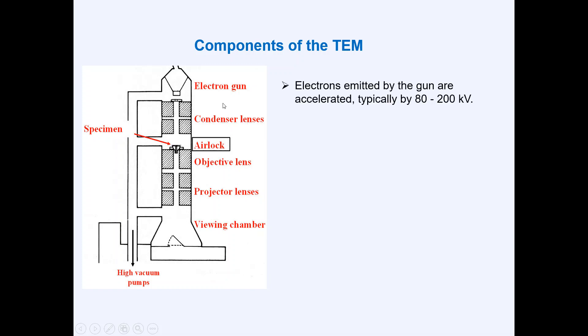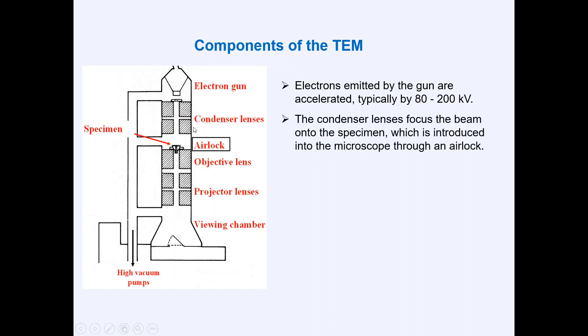Looking at the figure showing different parts of the transmission electron microscope: the topmost section consists of the electron gun, which emits electrons. Emission is achieved by applying a high voltage to the electron gun, which is normally made of tungsten or lanthanum hexaboride crystal. After emission, the electrons are accelerated toward the specimen using a high voltage that ranges from 80 to 200 kiloelectron volts.